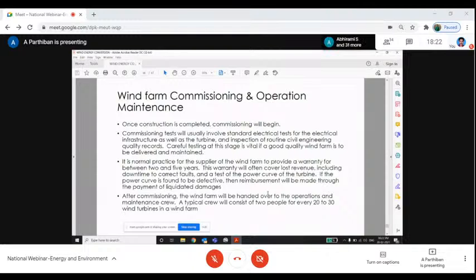then we need to have some approvals from particular nodal agencies: commissioning approvals, safety certificate, all the approvals. Then on the particular commissioning day, the WTG will be put in generation mode. Once the WTG is in generation mode, that particular wind farm will be handed over to the operation and maintenance team. This operation and maintenance team generally will have around 2 to 3 people for 20 to 30 turbines. If we have a 300 megawatt wind farm, around 20 people will be there.